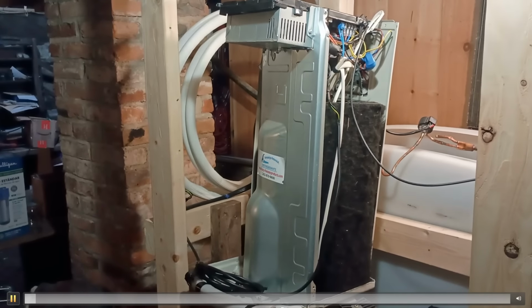The cons are that they have low heat output when it is coldest outside, so you need to oversize the system. So if I need a 24,000 BTU system, I actually need to buy a much larger system. Let's get into a little bit of that. Here is a chart of outside air temperature versus the output of that system, and this is for a set temperature inside of 70 degrees Fahrenheit. If the outside air temperature is 38 degrees, this unit will output 18,000 BTUs. It's an 18,000 BTU system, so it actually puts out that right at 38 degrees.